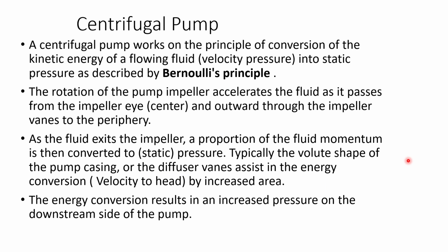Centrifugal pump works on the principle of conversion of the kinetic energy of the flowing fluid, and it converts velocity into static pressure as described by Bernoulli's principle. The rotation of the pump impeller accelerates the fluid as it passes from the impeller eye, that is the center of the impeller, and outward through the impeller vanes to the periphery. As the fluid exits the impeller, a portion of the fluid momentum is converted to a static pressure. That is, the velocity is converted into a static pressure.